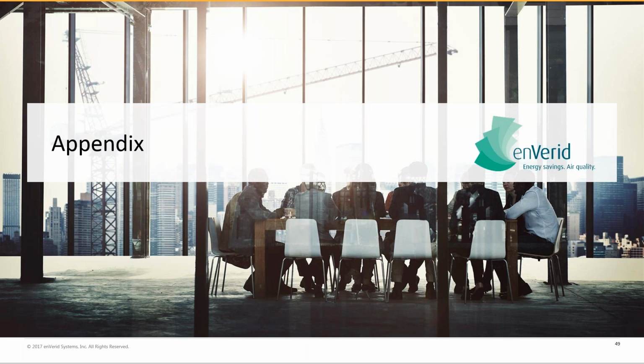Yeah. Okay, there's another question. Following up on how near is too near to an unusual source: to determine the answer to that, with ASHRAE 62.1, are physical contaminant measurements taken on the site to determine how close is too close? Yeah, so we can do that. You're supposed to do that for the ventilation rate procedure every time. So you're actually supposed to reference outside air quality.